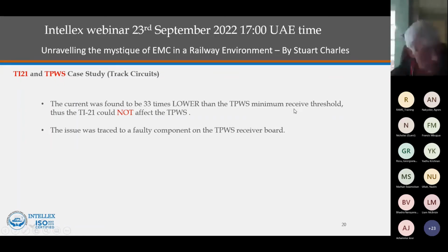The issue was actually traced to a faulty component on the TPWS board. There were about 2 boards with a faulty component from the manufacturer. They were out of spec, and we analysed it - we undertook a root cause analysis and found this was the cause. However, the anecdotal evidence, I guess, still stands amongst the people who weren't involved with this. But it does show you how EMI could theoretically, unless you go through quite a detailed analysis, affect different systems. And of course, this is safety critical.